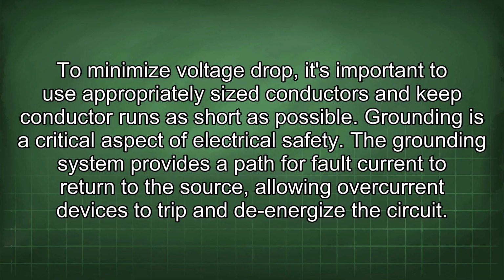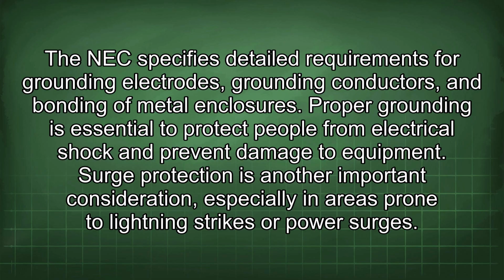Grounding is a critical aspect of electrical safety. The grounding system provides a path for fault current to return to the source, allowing overcurrent devices to trip and de-energize the circuit. The NEC specifies detailed requirements for grounding electrodes, grounding conductors, and bonding of metal enclosures. Proper grounding is essential to protect people from electrical shock and prevent damage to equipment.